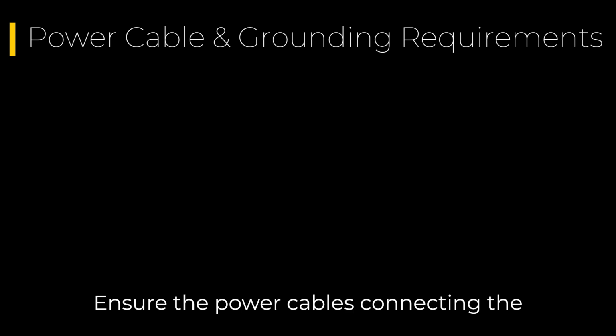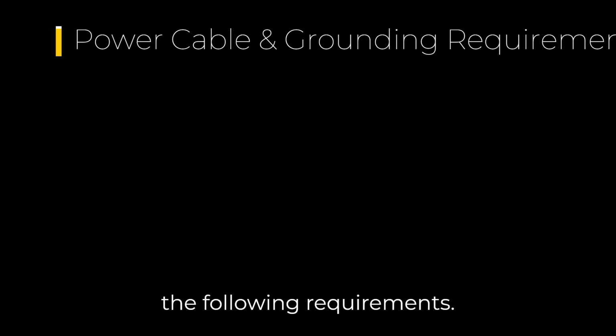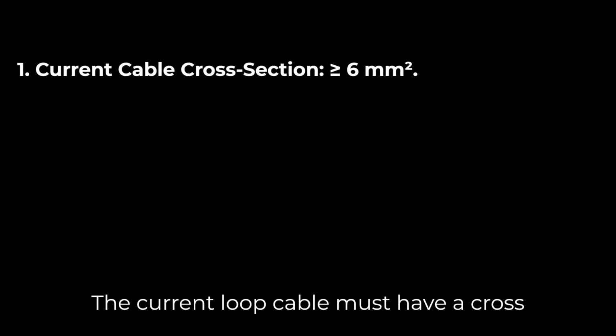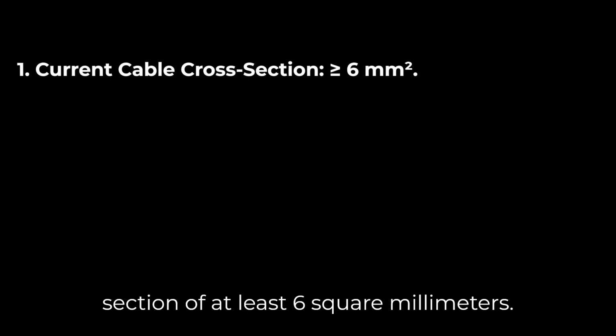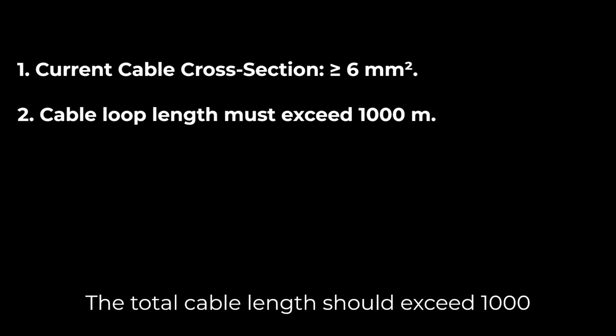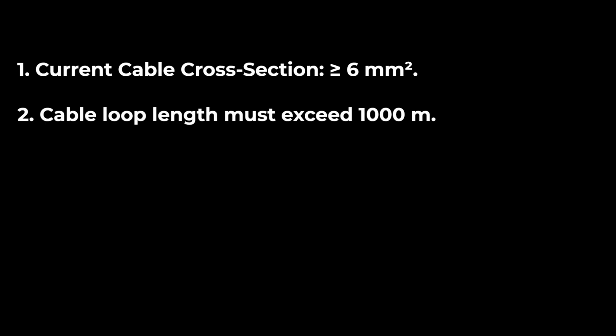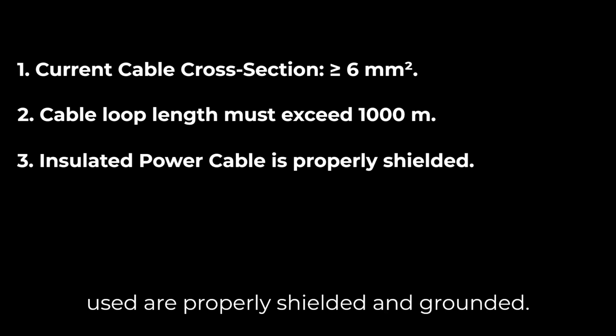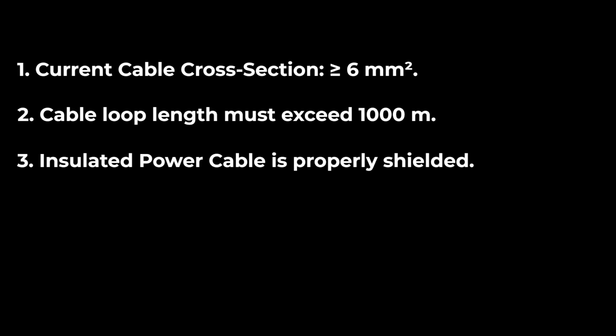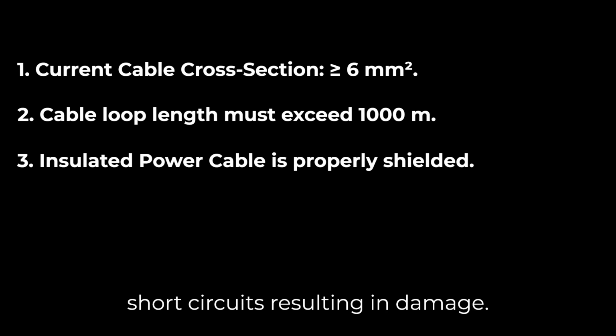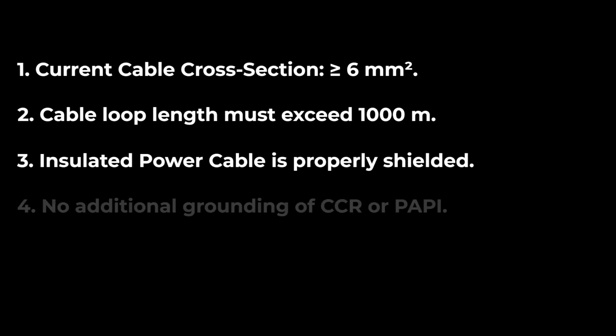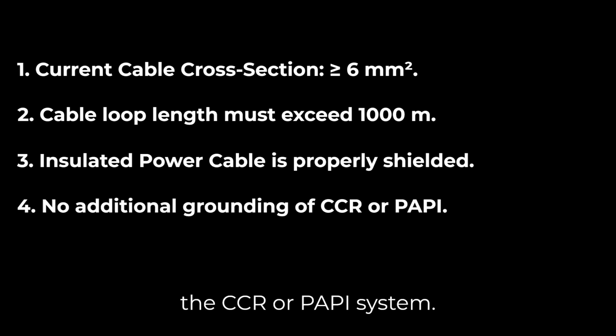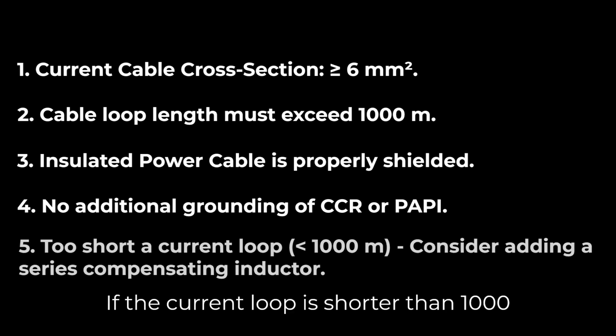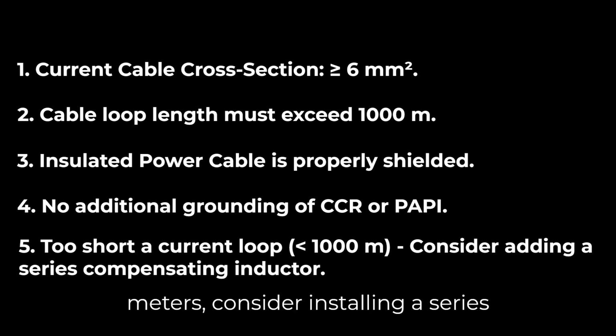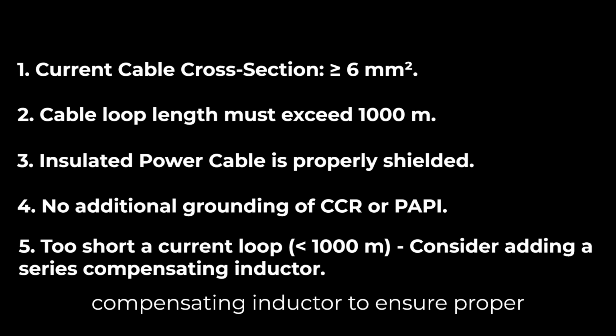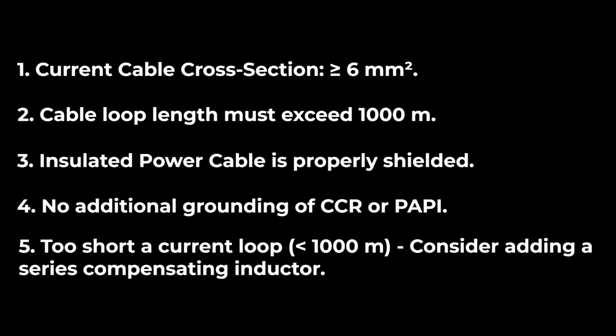Ensure the power cables connecting the CCR to the isolation transformers meet the following requirements. The current loop cable must have a cross-section of at least 6 square millimeters. The total cable length should exceed 1,000 meters. Ensure that the insulated power cables used are properly shielded and grounded. This prevents current leaks or potential short circuits resulting in damage. Do not apply any additional grounding to the CCR or PAPI system. If the current loop is shorter than 1,000 meters, consider installing a series compensating inductor to ensure proper circuit impedance and reliable operation.